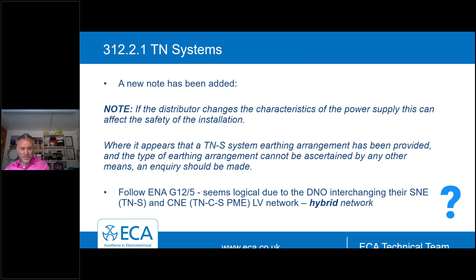And that's because the DNOs now, through Engineering Recommendation G12.5, which relates to PME networks and hybrid networks, are repairing the networks with hybrid cables. So where you think traditionally of using a lead sheath cable, and that's TN-S, it's probably been repaired down the road and is now PME. So there's a little note there saying that you probably want to consider that to be TN-C-S PME, and you should inquire with the DNO, who can potentially confirm it's actually a PME network. So that's a most welcome note there.